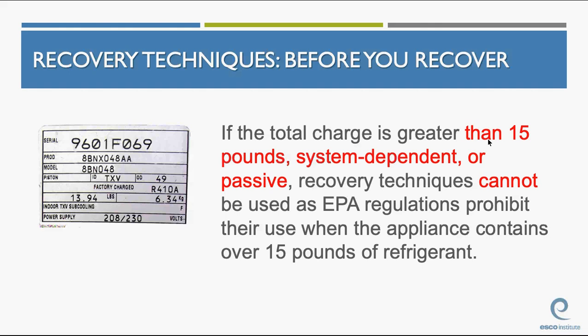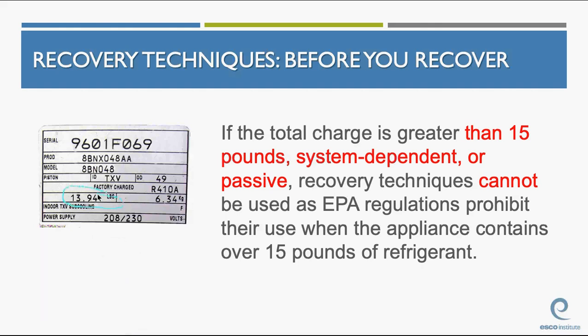So if you look at the label there, could you use passive recovery on that system just by the label? Anybody? Yes. However, if all of a sudden you have 25 foot of line set, that line set has additional charge in it. So you might be pushed over just by line set. Guys, you do not want to sit here for the 7 hours it's going to take to use the passive recovery. So we're talking EPA regs, but not what you would actually do.